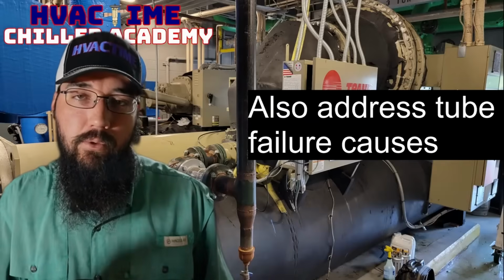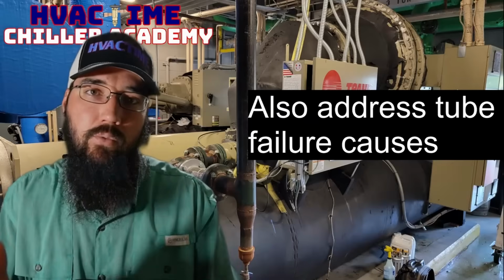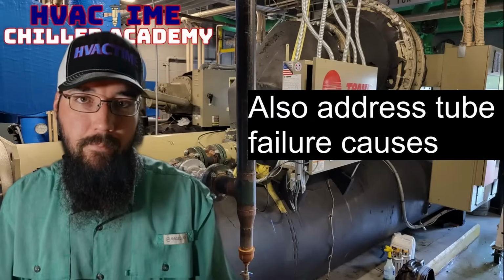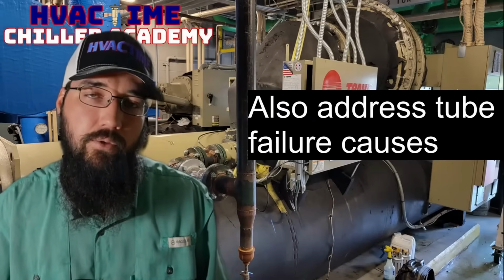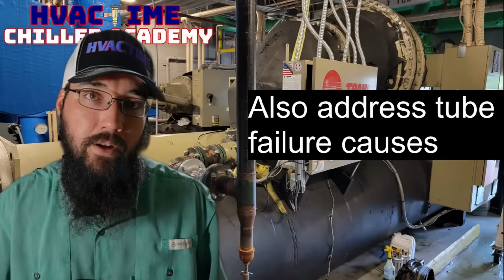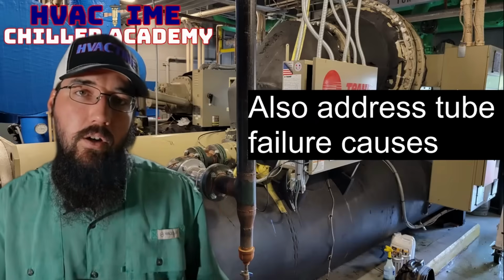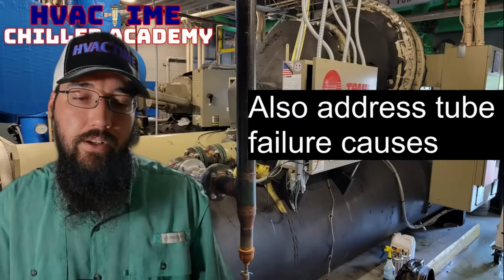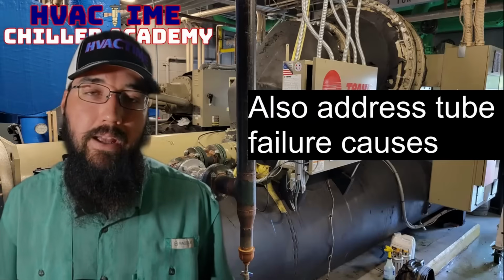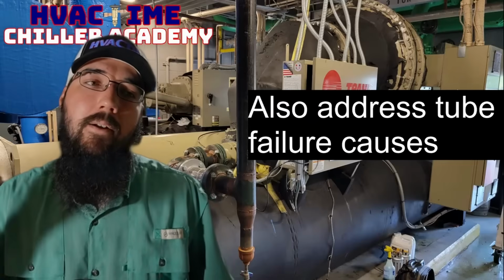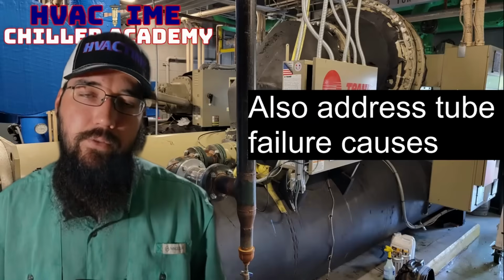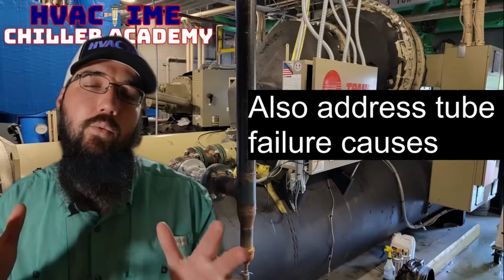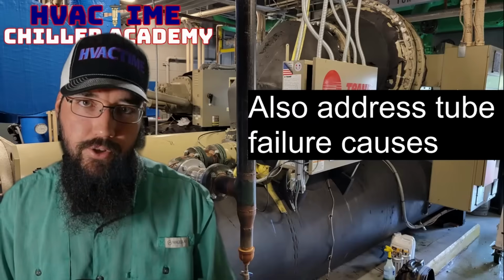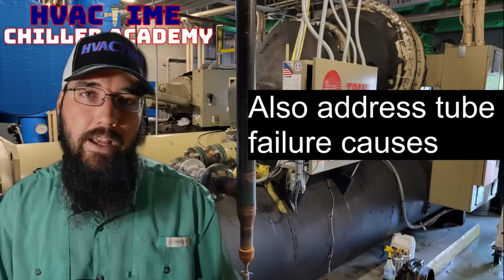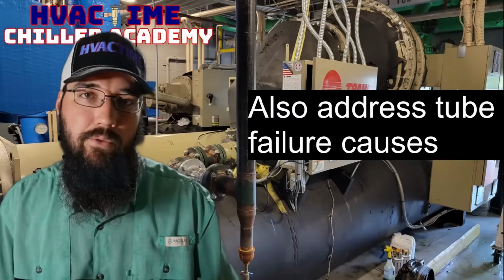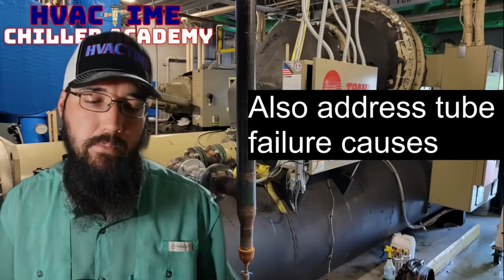Now, if you're not following proper practices, you will very likely have liquid refrigerant making contact with tubes that still have water in them. And if you are not flowing water through those tubes, or if you have not drained that barrel, either way, that water that's sitting still will freeze and will rupture. And you've got a really bad day on your hands at that point. So call it malpractice, if you will, or just ignorance with recovering and charging procedures. You can freeze water in a tube and cause it to fail or rupture or bust.